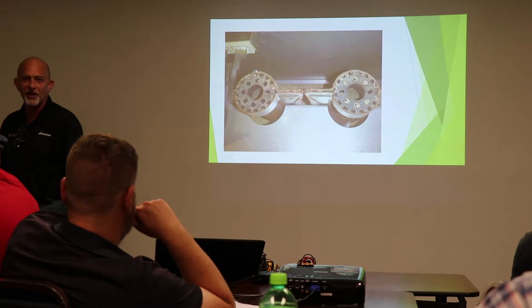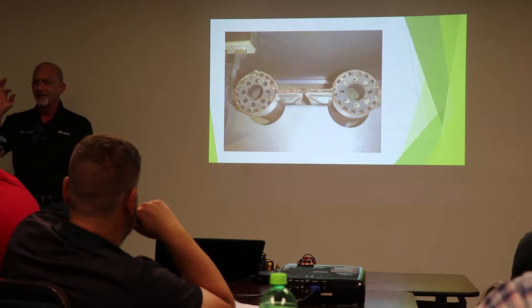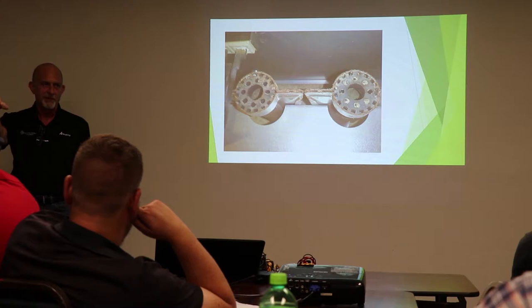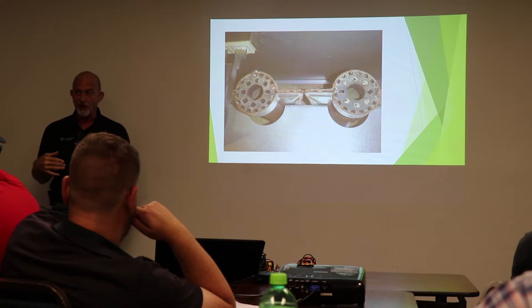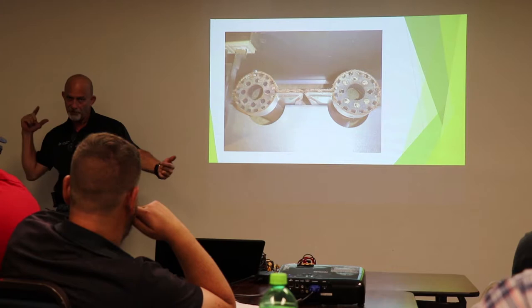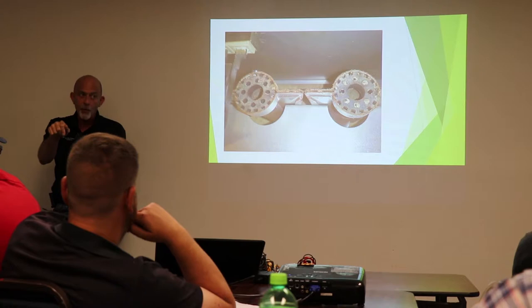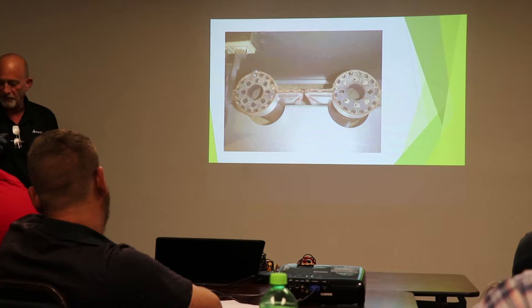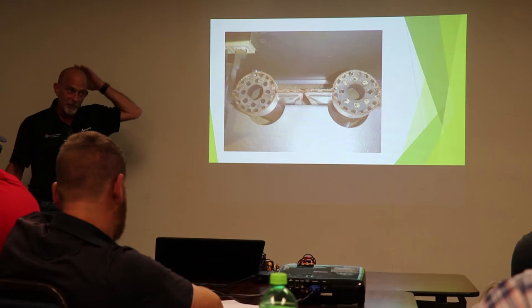And if you're at the front door of the furnace, you hear a boom. You see it suck in sometimes. See it suck in? I've seen them blow the sight glass out of some furnaces. Pops them out. Personally, myself, I like watching stuff light off. Be careful, especially when we talk about boilers. Ribbon burners, they get rolled over, they will light too. And when it does, it shoots at you. So be very careful if you're like me and you like watching stuff light off. Okay? I don't have to worry about losing hair, but heat exchanger was fine, right?